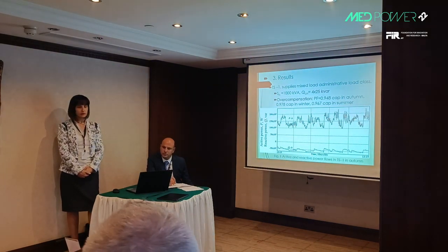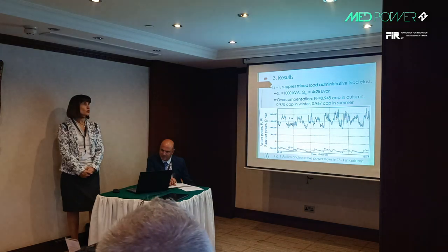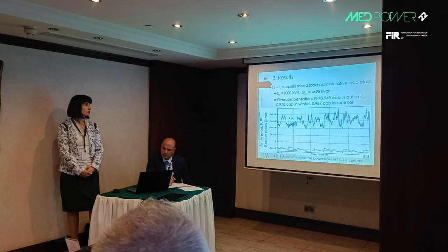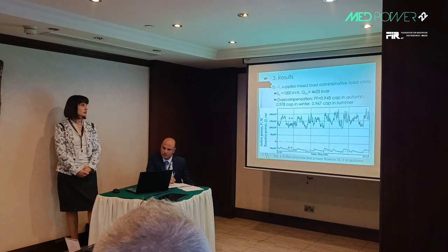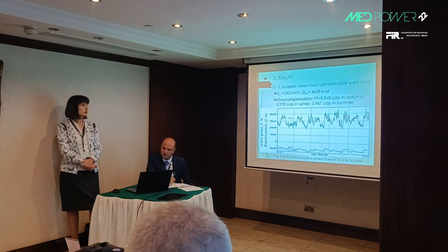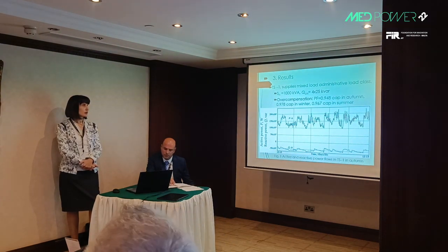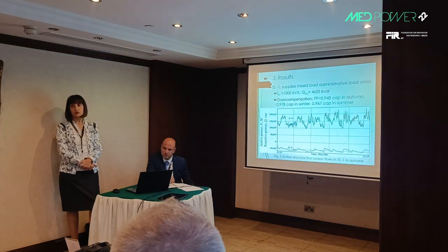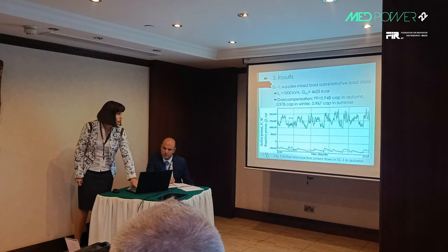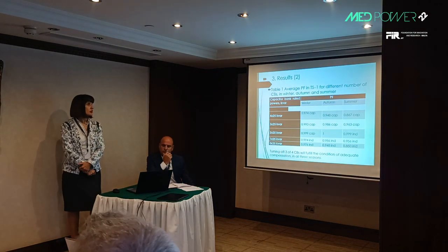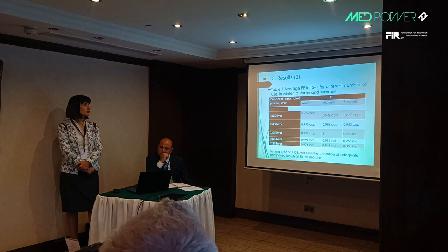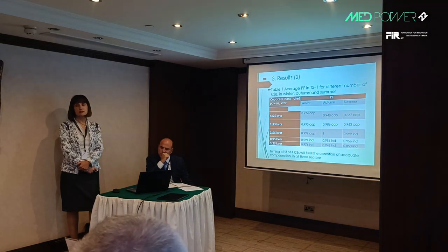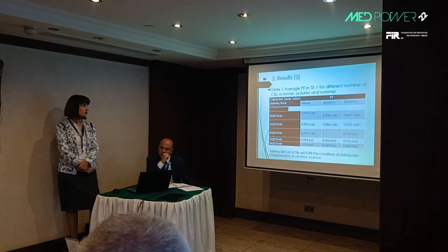As an example, transformer substation 1 is selected. It is found that overcompensation occurred in all seasons, which is visible in the graph because reactive power is negative. It is also found that uninstalling three capacitor banks should bring the power factor into the proper range, and that only one capacitor bank with a rated power of 25 kvar should be sufficient for this transformer substation.